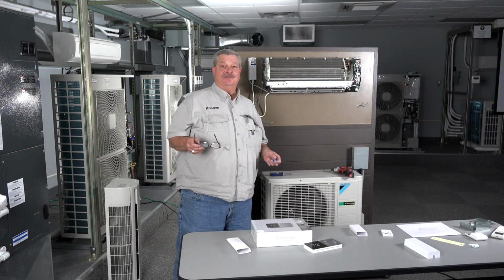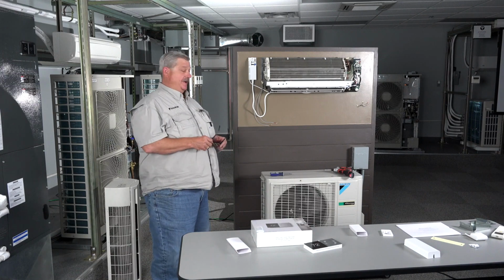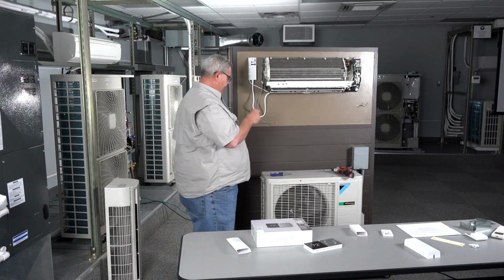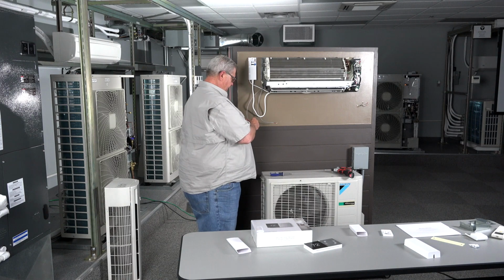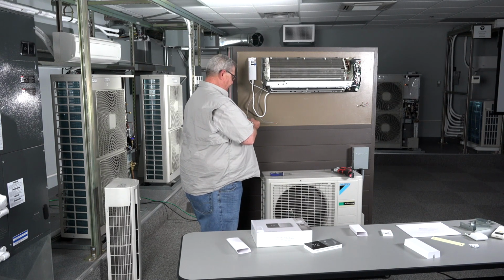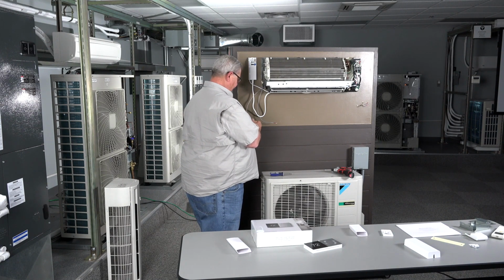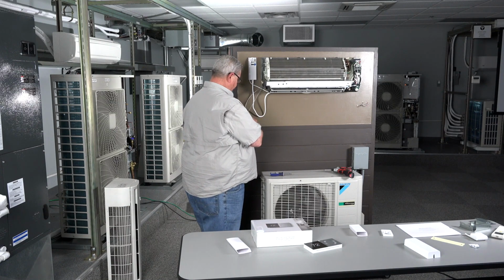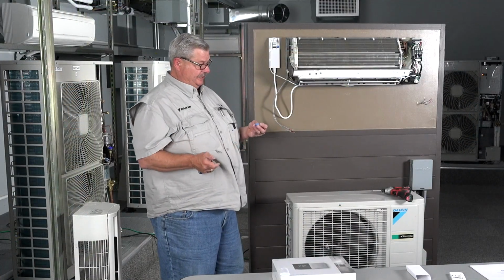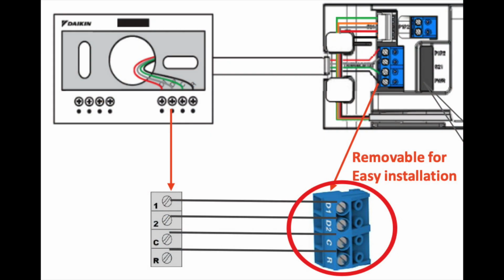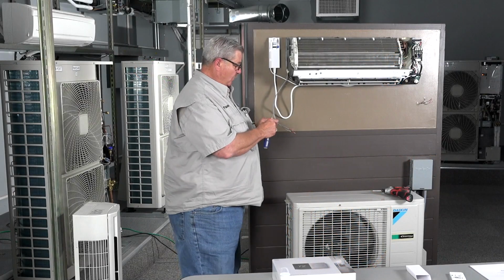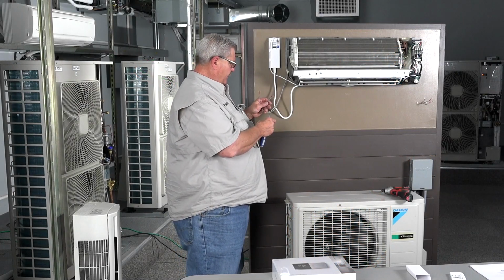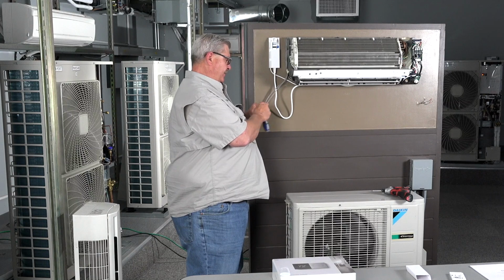So with the wires stripped, we're going to go ahead and make our connection to the translator. There again, I use two 18-2 stranded non-shielded wires. I have marked one of the wires to be my 24 volt power on each end. You will see the terminal strip is marked R, C, D2, D1. R and C being our 24 volt power, which is the cable that I have marked.